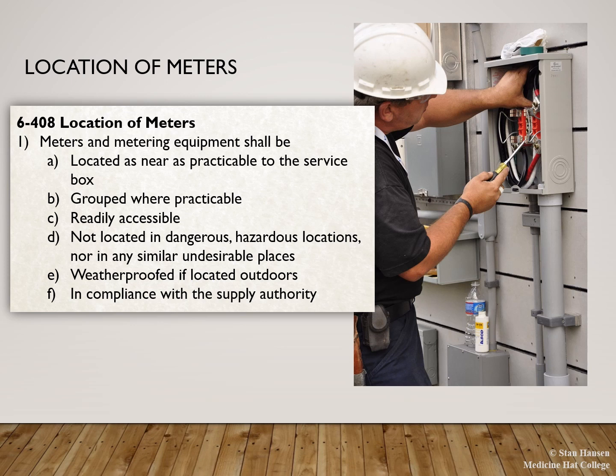For example, in Medicine Hat, we make sure that we mount the meter base on the corner closest to where the utility enters the property and within 2 meters of that corner. This makes sure the meter base doesn't go too far into the property to affect voltage drop, as well as that 2-meter rule allows for any brick molding or stone molding to go around the corner without impeding it.